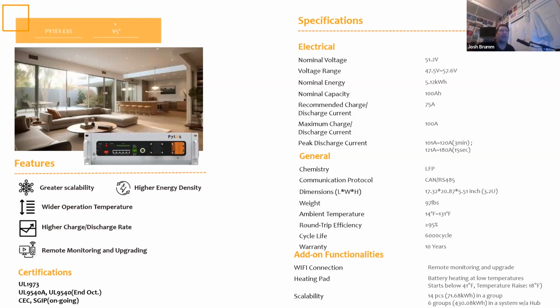6,000 versus 4,000 life cycles—lithium iron phosphate versus NMC, both at 90% depth of discharge. That's a 2,000 cycle difference. 2,000 divided by 365 is 5.47—that's almost 6 extra years of life versus the NMC chemistry at the same exact depth of discharge.